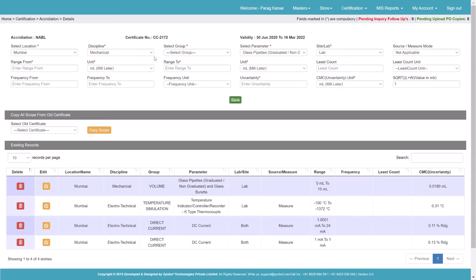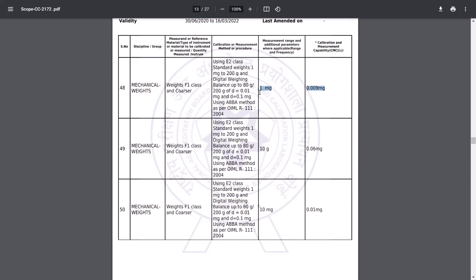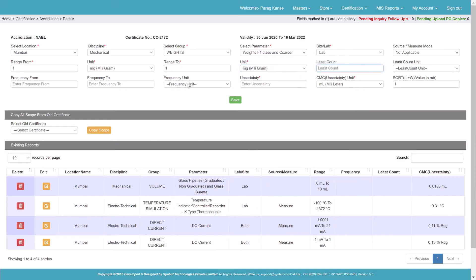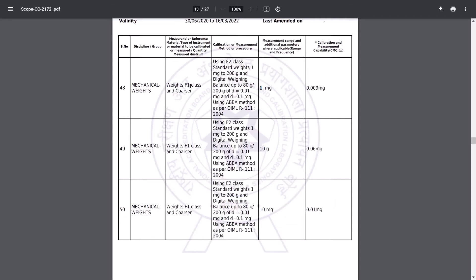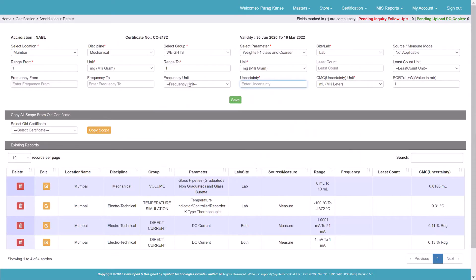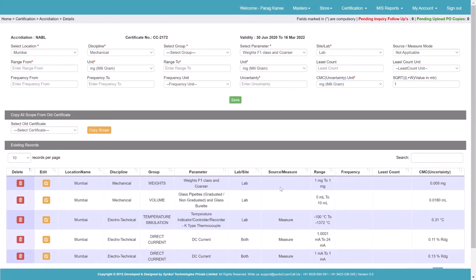In this case, we'll select Mechanical, then Weights, then F1, lab source, measure not applicable. The range is 1 mg to 1 mg — because a weight doesn't have a range, it has a specific value, so we enter 1 mg to 1 mg. There is no least count, and the uncertainty is 0.009 mg. We enter that and save it.